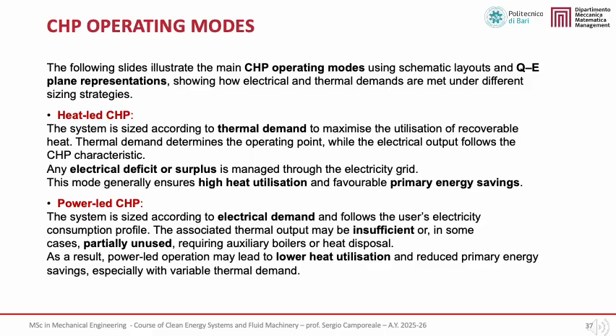Moreover, if recoverable heat exceeds the instantaneous thermal demand, part of the available heat may remain unused unless thermal storage or additional heat sinks are available. As a consequence, power-led CHP systems may lead to lower overall heat utilization and reduced primary energy savings, especially in applications with limited or highly variable thermal demand. For this reason, EU design guidelines stress the importance of carefully analyzing thermal load profiles when adopting a power-led approach.